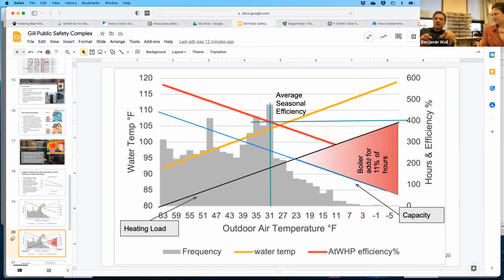So I'll just explain. The reason we're showing you this is that we've specified a heat pump for you. And rather than having you buy a third heat pump to make up for this 11% of the hours, we're suggesting you buy just the two that would satisfy almost 90% of your heating season, and then use your existing perfectly good boiler to make up the difference, rather than over-specify to deal with this small portion of time.